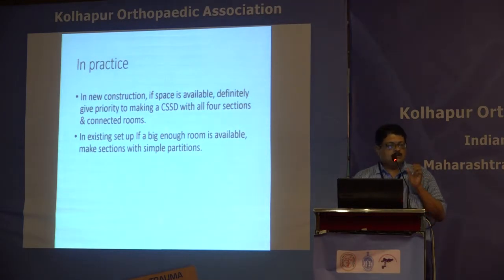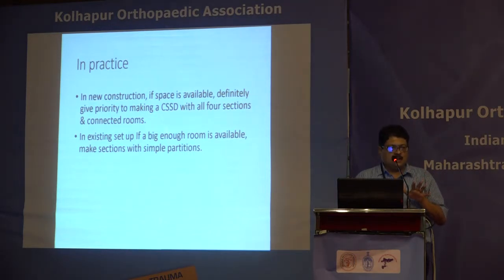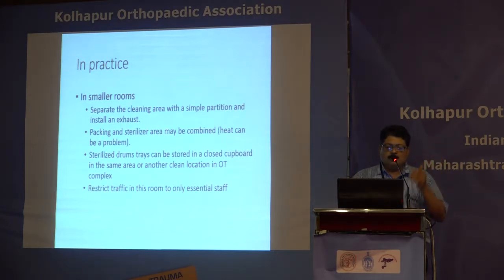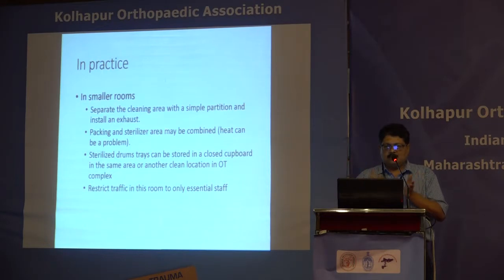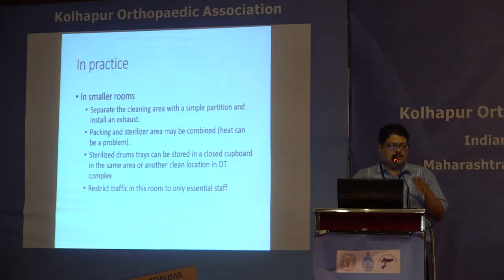In practice, if you have the space you can fit in four separate areas; if not, the four activities can be done in the same room using simple partitions. At minimum, separate only the cleaning area, since the other three areas are all clean areas that can be combined. The dirty area should be separated with a separate exhaust, packing and other clean areas can be combined, and sterile material can be stored in closed covers in the same area or elsewhere in the OT complex. It is important to restrict traffic in this room, as more people means higher risk of recontamination of washed instruments.